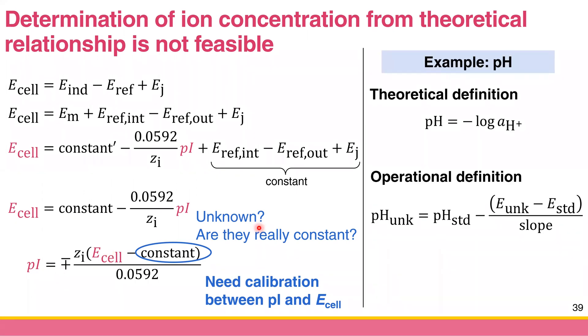To summarize: when we talk about pH, in theory we define pH as the negative base-10 logarithm of the concentration or activity of the proton. But this is very hard to determine experimentally. So we use an operational definition instead — we find the pH from calibration. The main concept is that you need calibration; you cannot find it from theory.